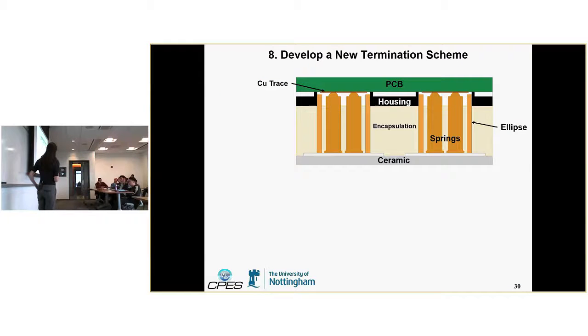This is a cross-section view. These are the elliptical shields and these are the springs. What if you have a PCB that mates with the housing material so it's sealed, meaning you don't need to worry about creepage between this terminal and that one. But you still have these air gaps here, and anywhere you have air, you have a place where partial discharge can occur.